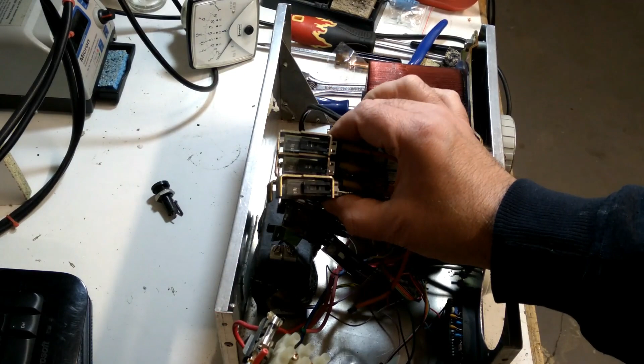Now the reason why I did this system is so that when I switch between scales, it doesn't matter if the contacts on the relays aren't making the best contact. That means the current I'm reading is always going to be accurate, because if the contact of the relay has high resistance, for example, obviously the current is going to read lower.